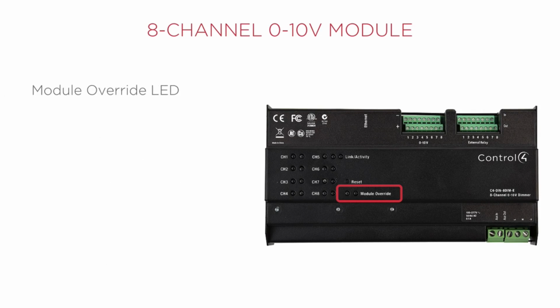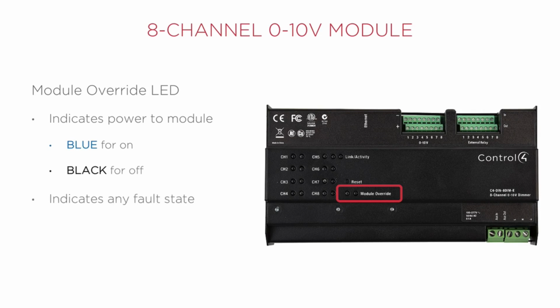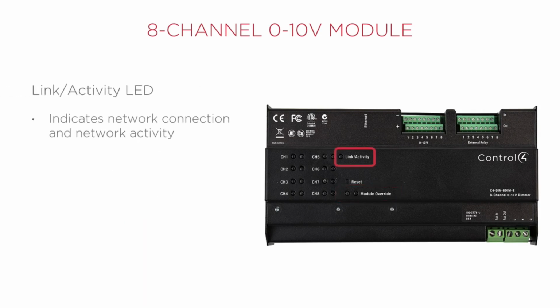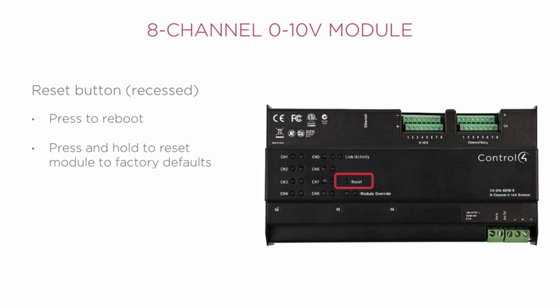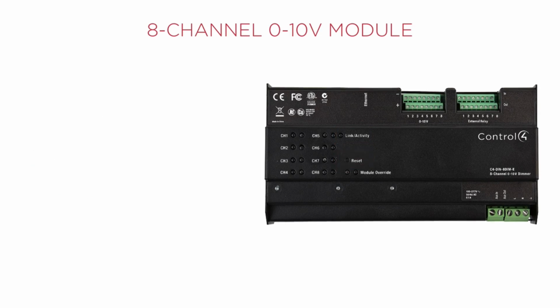The module override LED lights up blue if the module is powered up or black if it's not, and indicates a fault state. The LED will light up red if the module itself is overheating. The link activity LED lights up green if the module is network connected, and orange if there is activity through the network to the module. There is a recessed reset button that can be pressed to reboot the module, or pressed and held to reset the module to the factory defaults.